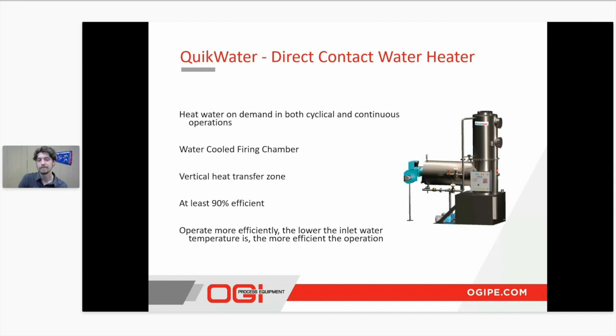And then lastly, the feed water. For a boiler, you may have to have a deionized, demineralized, softened water for your boiler system. Whereas the QuikWater, especially if you're using it for rinse solution, you can tie directly into your city water line. That hardness won't matter as much for a QuikWater, especially if you're just using it in a 3-month to 6-month time span. You're not really going to be noticing that scale buildup you may have over an 8-month period, or sorry, 8-year period of usage.